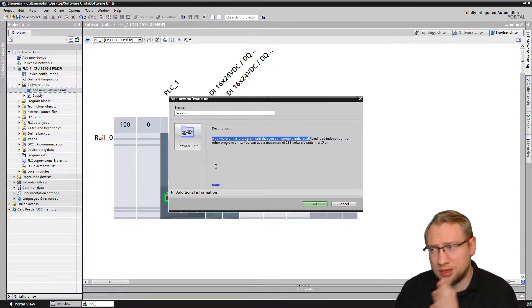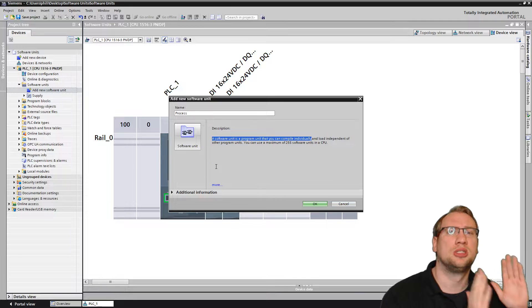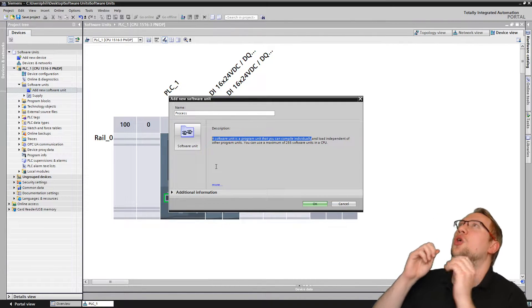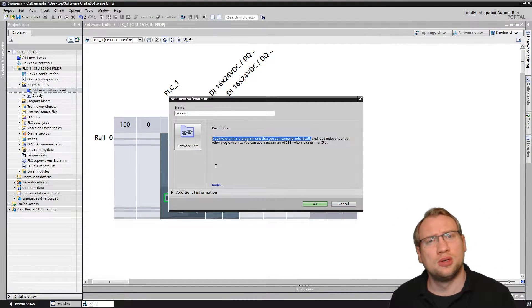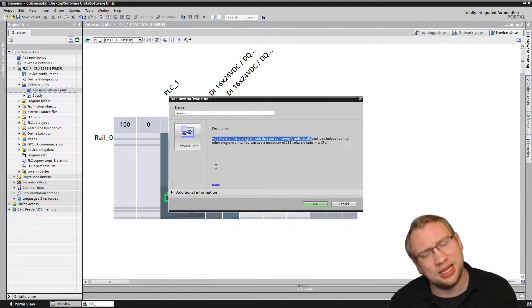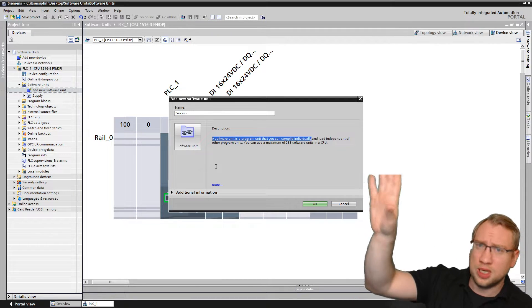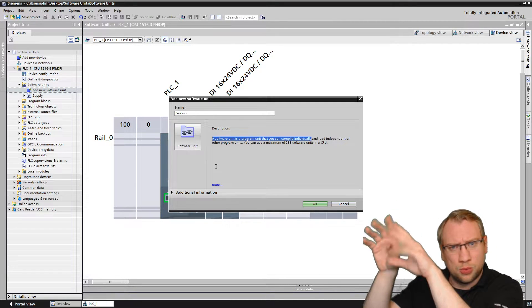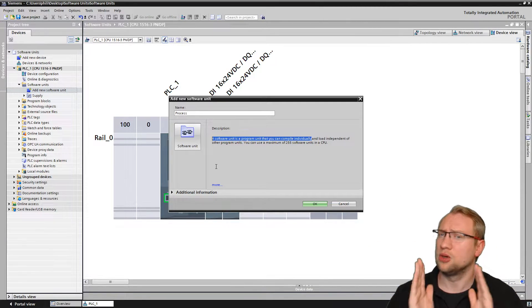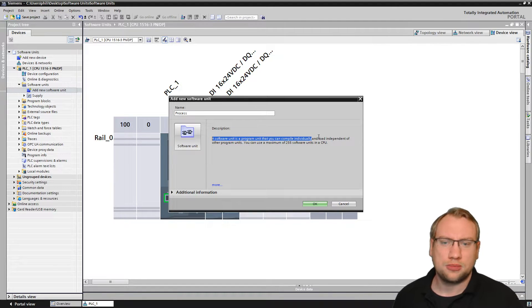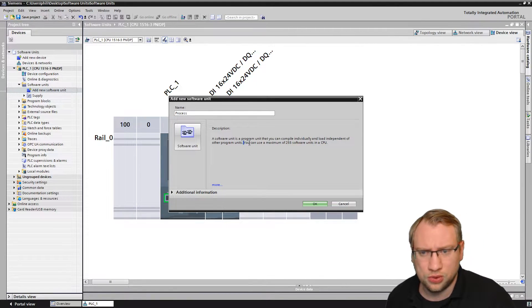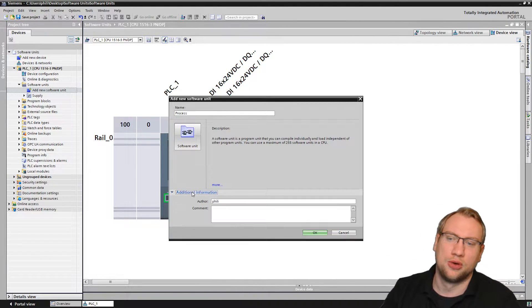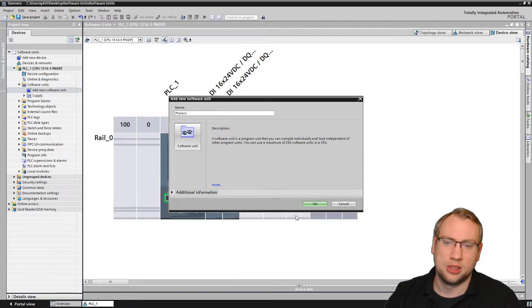The description says a software unit is a program unit that you can compile individually — that's great. Two people can compile independently, and if there's an error in one, the other still works. With TIA Portal for 1500s, you always had the problem that either your whole program is okay or nothing — you can't download a program that has any errors. With software units, if one doesn't work the other does. You can download the working one; they are completely separate. You can use a maximum of 255 software units.